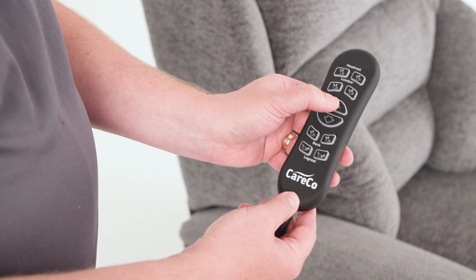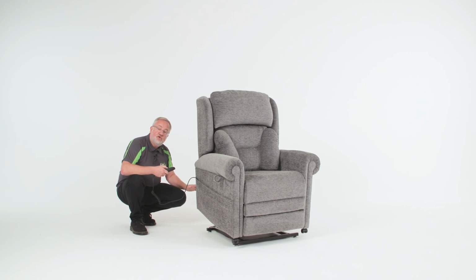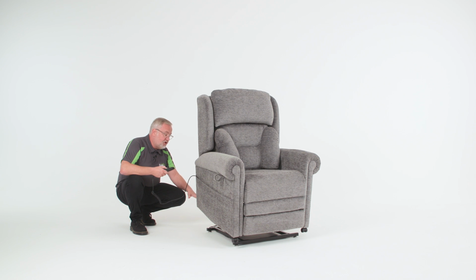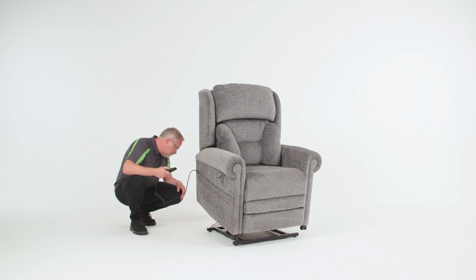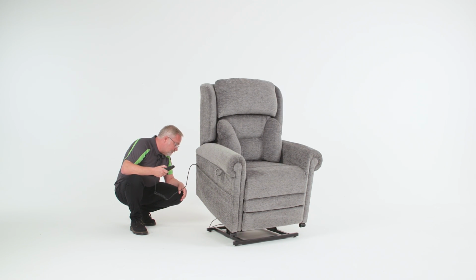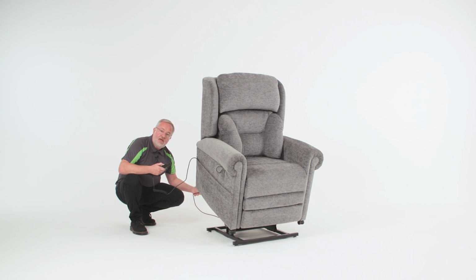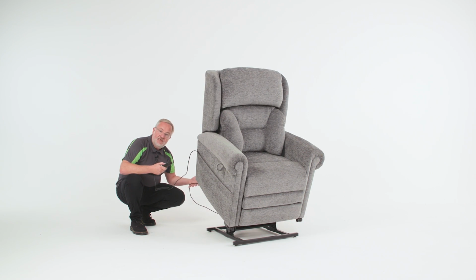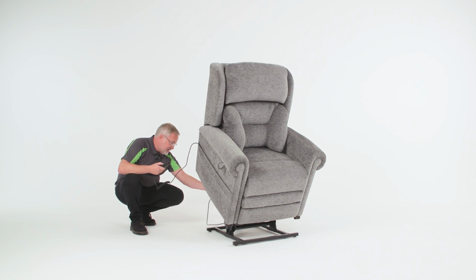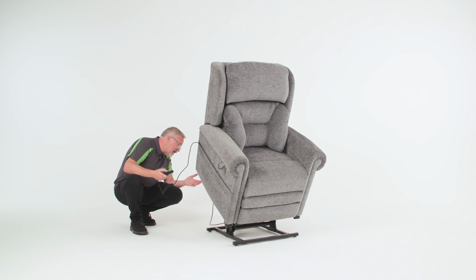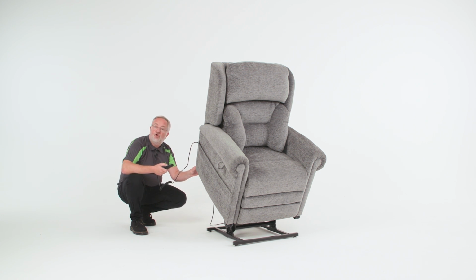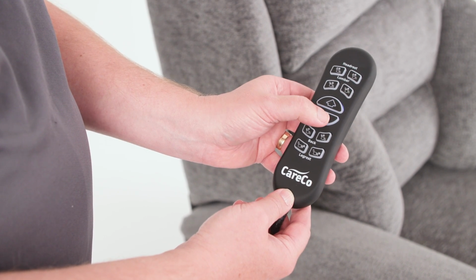So pressing the up button on the remote, I'm just going to visually look to ensure that none of the cables are going to catch. The cable that goes to the transformer needs to be free, which it is. With the chair fully raised, I can see that all the cables are present and correct. I can now bring the chair back down by pressing the down button.